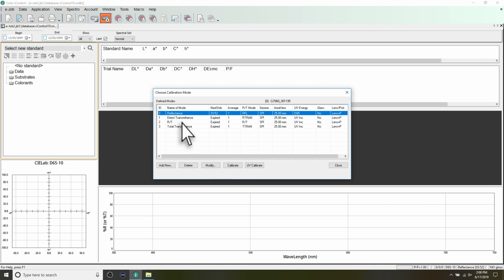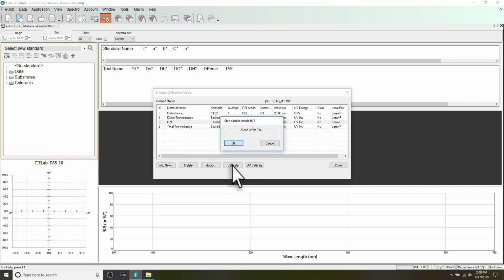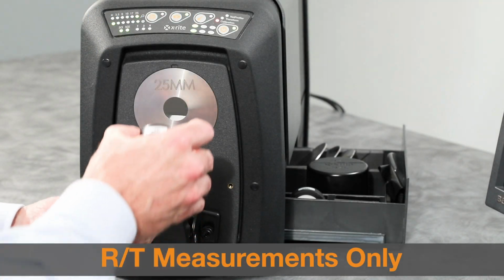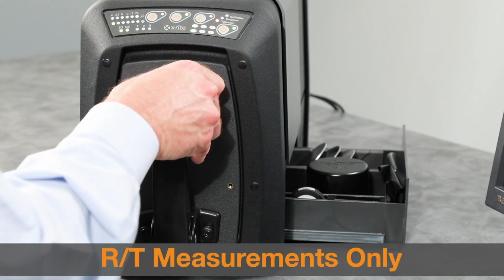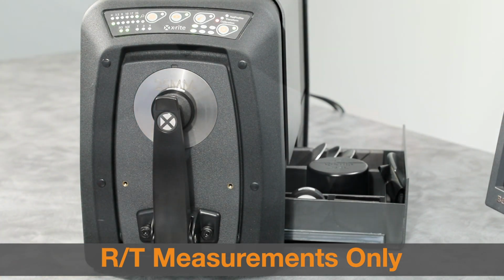Select the mode you wish to calibrate and click the Calibrate button. A calibration can also be triggered by clicking this icon in your application toolbar. If you're using Reflection Total Transmission mode, begin by performing a reflectance calibration.